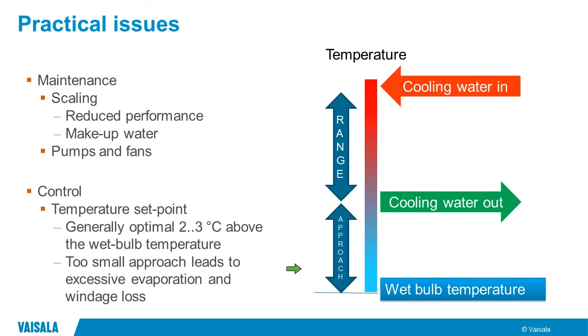Okay. So by using the wet bulb temperature, you can see directly if it makes sense to run your cooling towers today, or if it's a very humid day, you might not actually achieve any cooling to speak of, in which case you need to use other means of cooling your building.